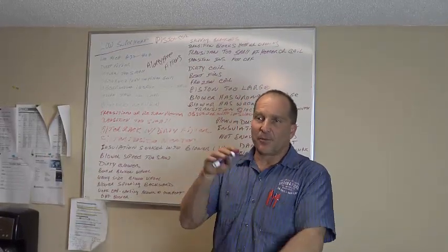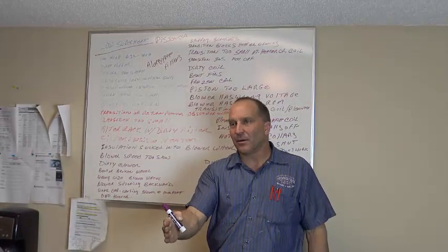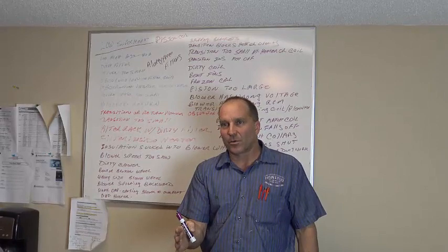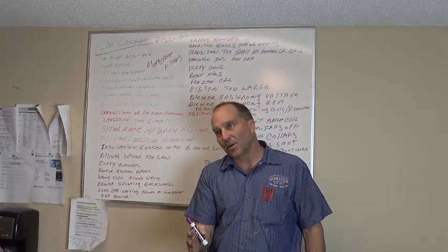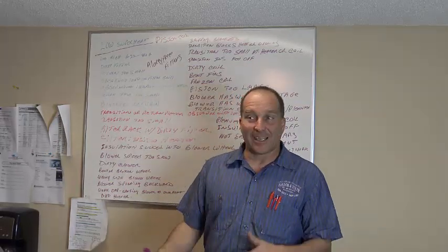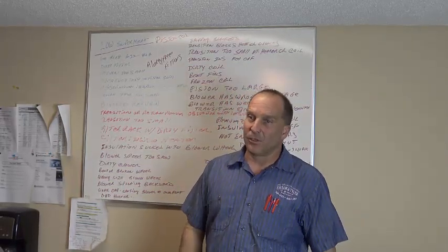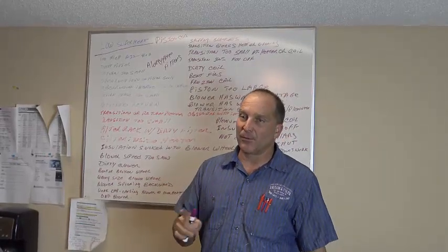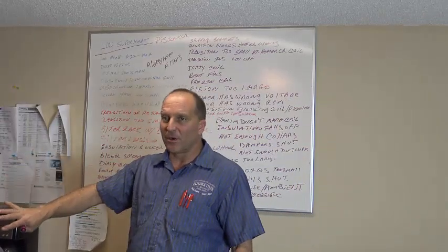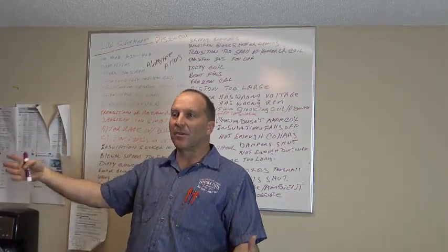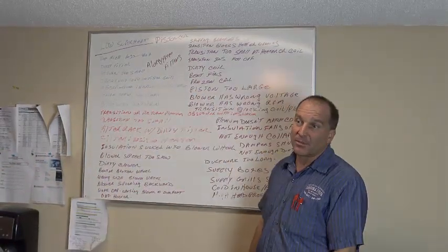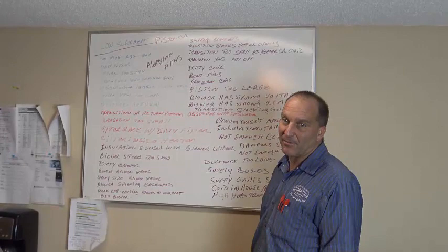So all that stuff keeps falling in there, so I left the heater filter inside of it, the original one, and they'd call me out once or twice a year, or whatever may be the case. It wasn't cool, and I'd go out there and I'd pull that filter out, clean the filter out, put it all back together. I'd tell them the filter's down there again, but nobody would ever go and change it. But if I pulled that filter out, the blower wheel would be filthy dirty, the coil would be filthy dirty, and it would cost them $600 to $700 to clean all this stuff, instead of $100 for me to go out there and pull the filter out and clean it. Big difference, okay? I help the customer out by leaving that filter in there.